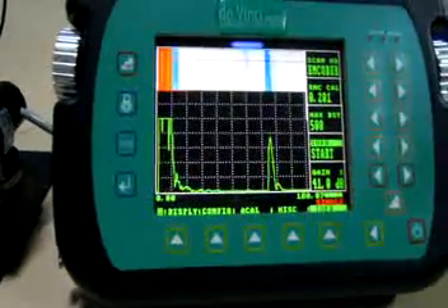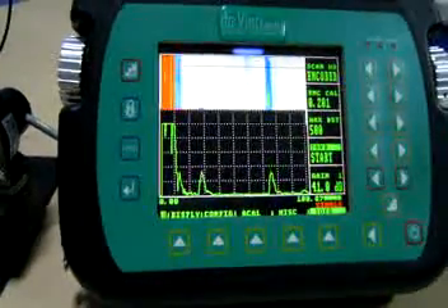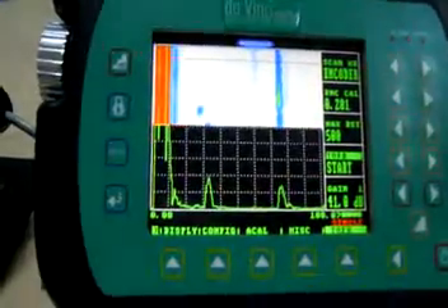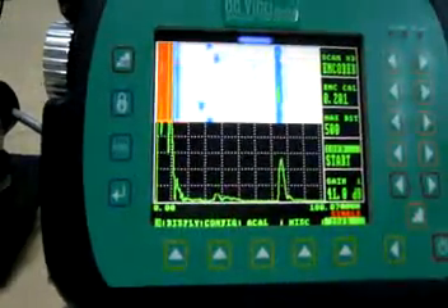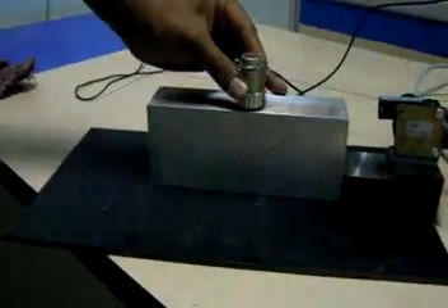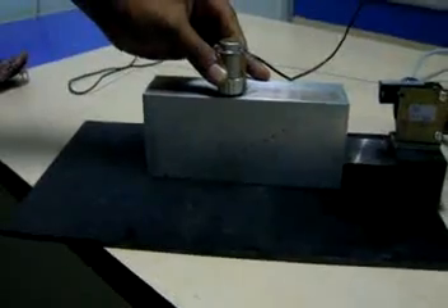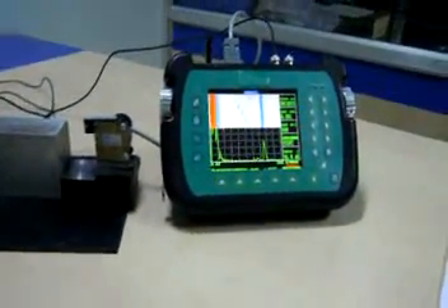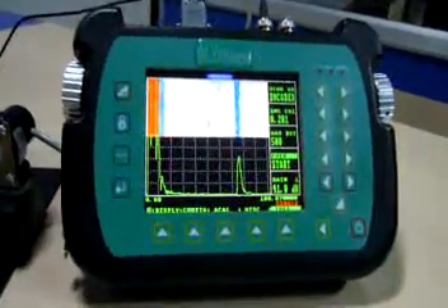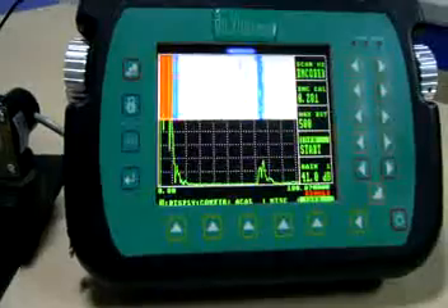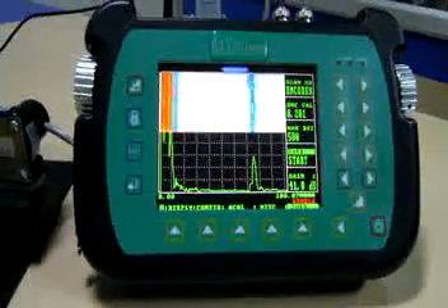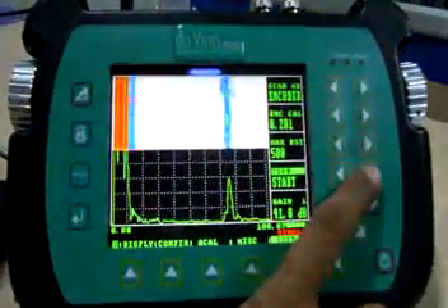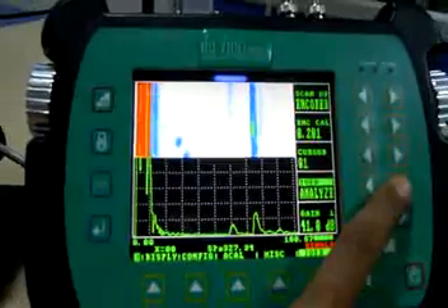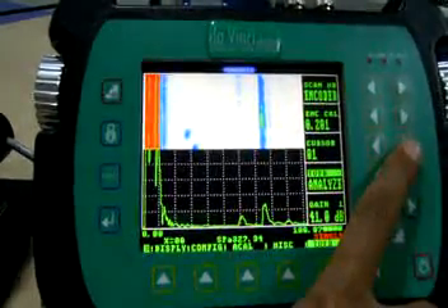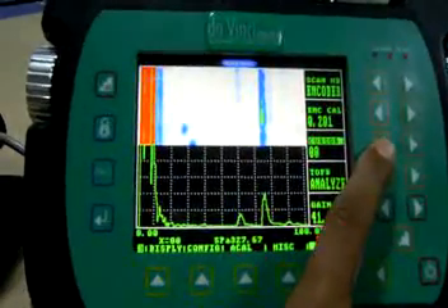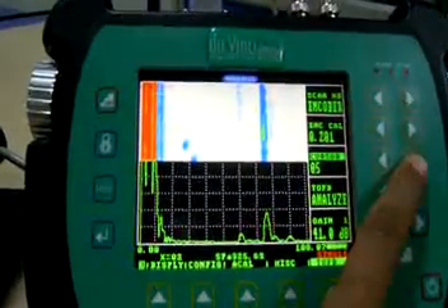So the upper half that you are seeing is the B-scan image, which some also call D-scan, and the corresponding A-scan you can see in the bottom half. After the whole scanning is done, as you are seeing here, this is the full setup. After the scanning is done, we can stop; a scanning length of 1 meter to 5 meter is possible. Now we are stopping the scanning process, and we can see that the data is still in the machine, and post-scanning analysis is possible.